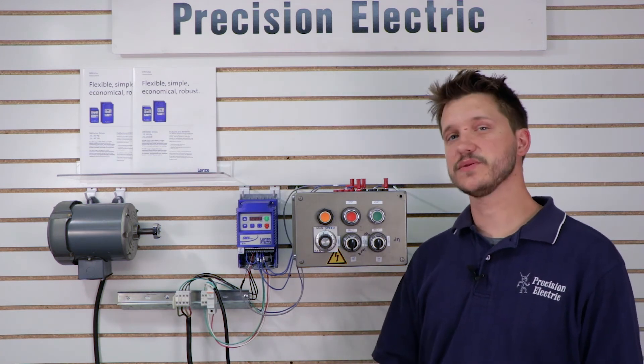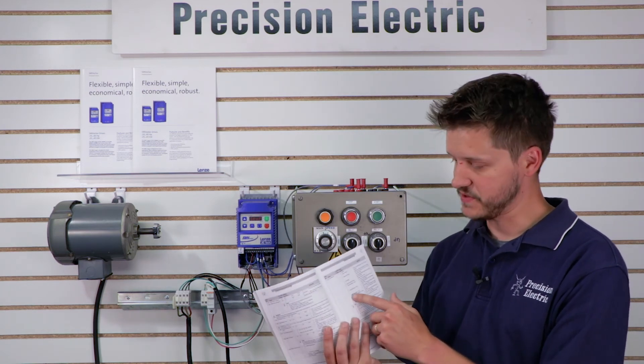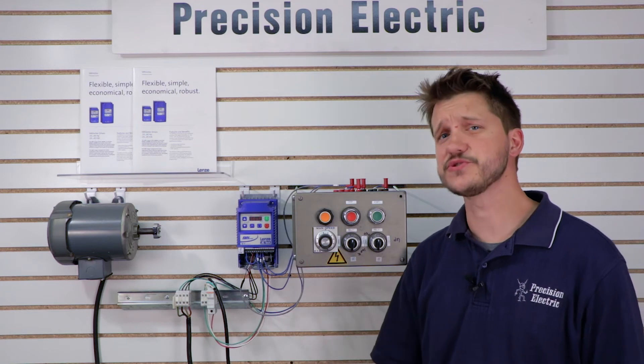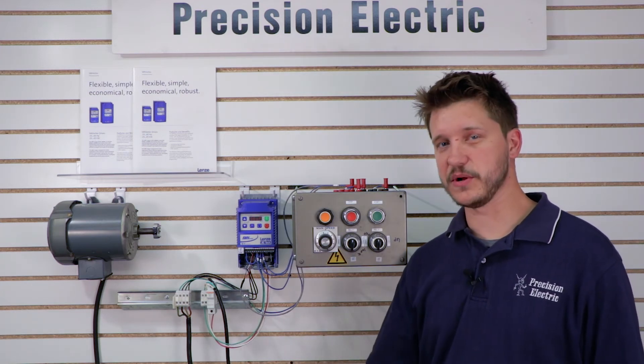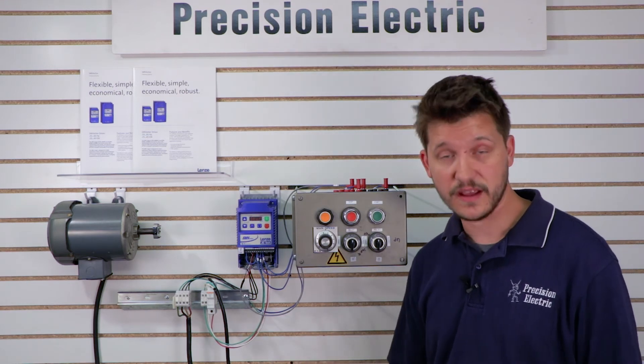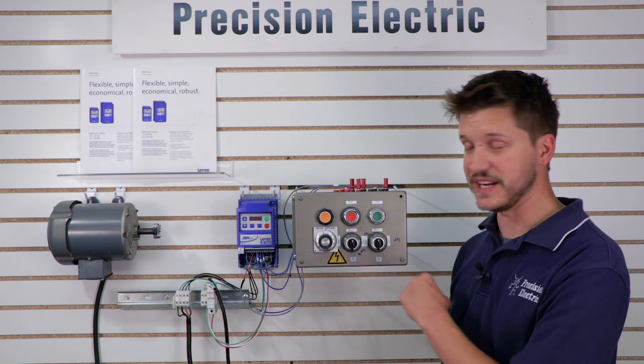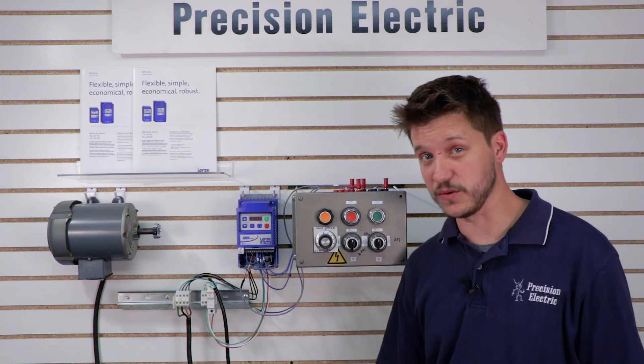For most customers, I would say they fall under that just start on power up or the standard auto restart. Those are usually the ones we end up talking to people about the most, because people either have it on a remote station, and they don't want to have to go out there every time it trips, they at least wanted to try to restart, or they don't want to have to apply a start command every time they turn on their drive. And so they just want to automatically start when they power it up.